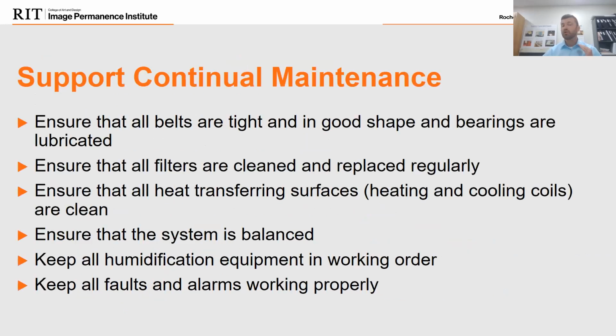For those of you in the collection, make sure you support that continual maintenance. Ensure that all the belts are tight and in good shape, the filters are being changed regularly, and all the heat transfer is working. I know it's easy to say, and you don't want to ride the facility staff, but it doesn't hurt to ask, hey, have we changed our filters recently?